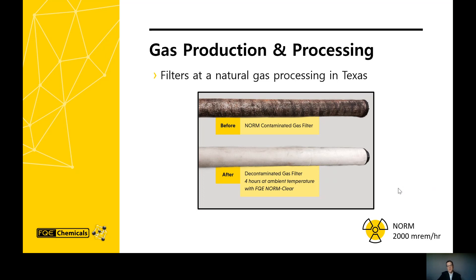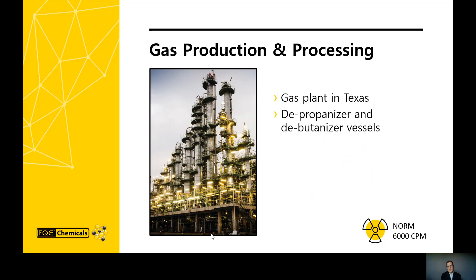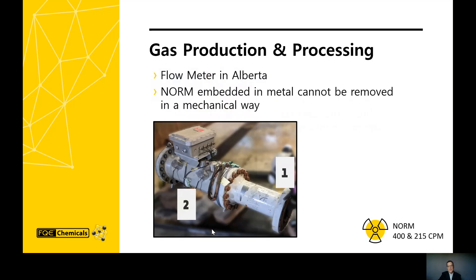An example where NORM has collected is shown here on a natural gas filter, which has collected enough NORM to measure over 2,000 millirems per hour. Another instance is shown at a natural gas plant in Texas, where NORM has built up inside the depropanizer and debutanizer vessels. The extent of the radioactivity was measured at 6,000 counts per minute, and the radiation could actually be detected on the outside of the vessel itself, traveling through the carbon steel. Here is a picture of a gas flow meter in Alberta where NORM was embedded in the metal even after mechanical cleaning, measured at 400 and 200 counts per minute — above legal limits — and thus the flow meter couldn't be put back into service.